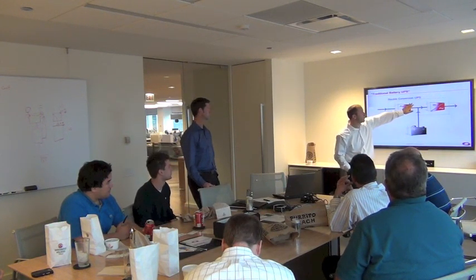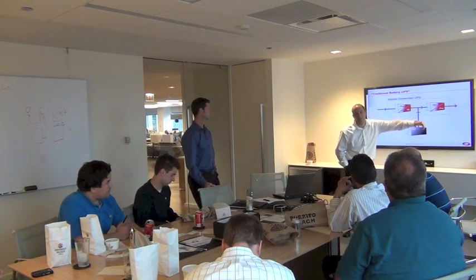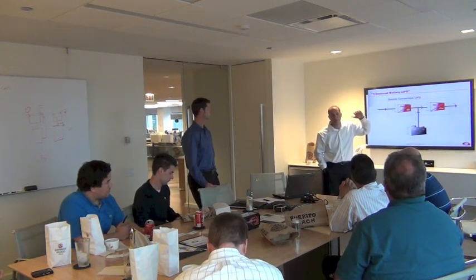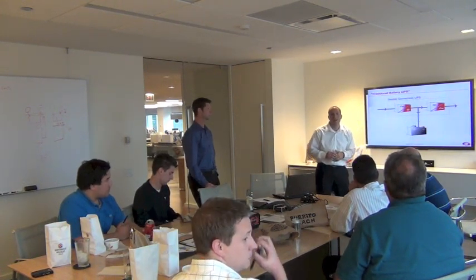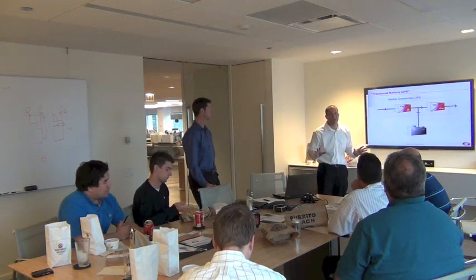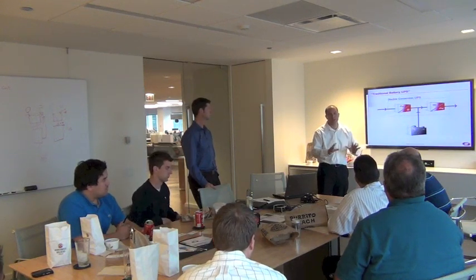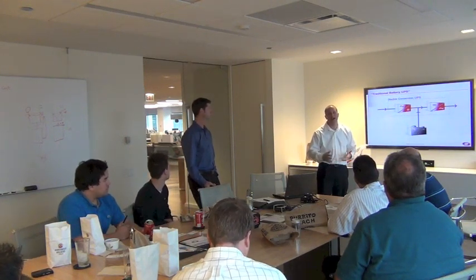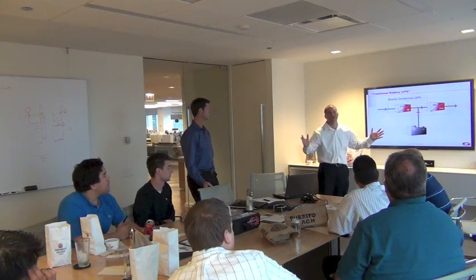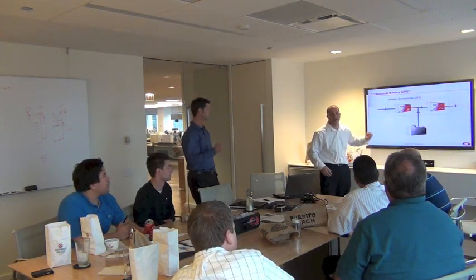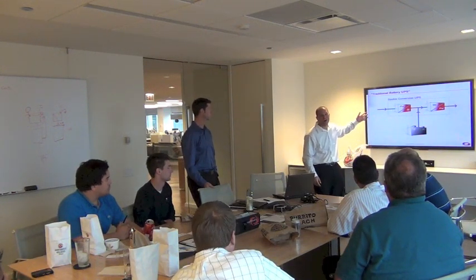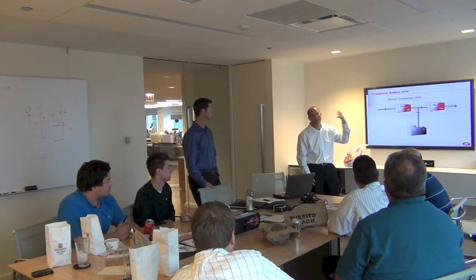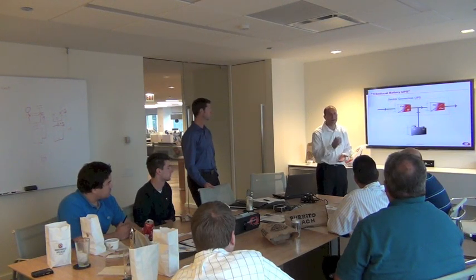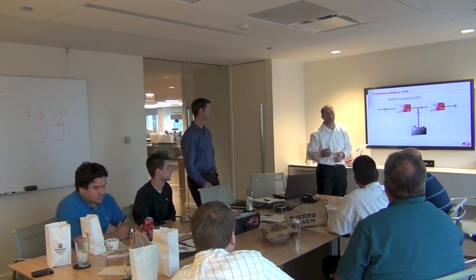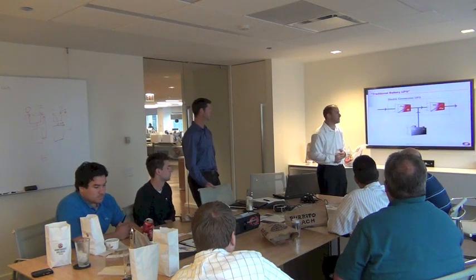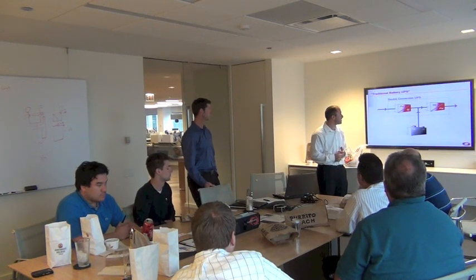So there's definitely no harmonic cancellation. You're passing all the harmonics back to the rest of your facility. So what's the impact to the rest of your facility if you have a really high harmonic load? Over time, what does it really look like for transformers and other equipment? What does your entire system efficiency look like? Are transformers and other parts of your facility running hotter if you're not providing that isolation to prevent harmonics from propagating through the rest of your facility? It's definitely an interesting approach.